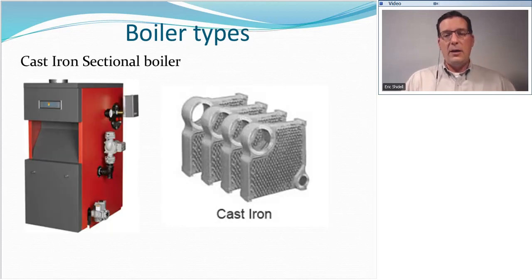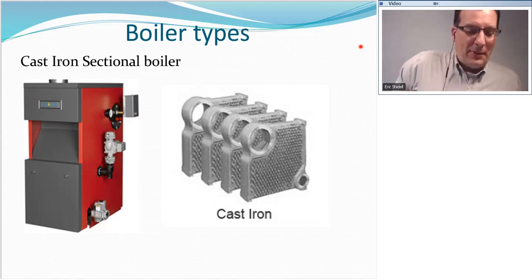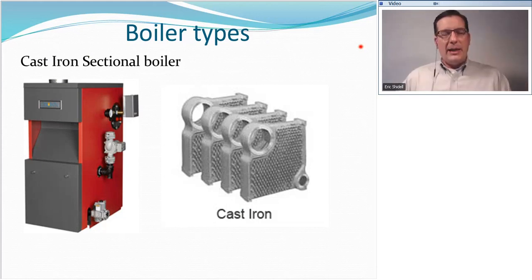All righty. Now we're going to get into the different types of boilers. The first type of boiler we're going to talk about is probably my favorite type of boiler. It is the cast iron sectional boiler. It is called cast iron sectional because it's made of sections that are made of cast iron. Each section is hollow. And here we see four sections side by side. And you can imagine that these are going to come together, and we're going to form waterways. Each section is hollow. And so water will enter on one side.